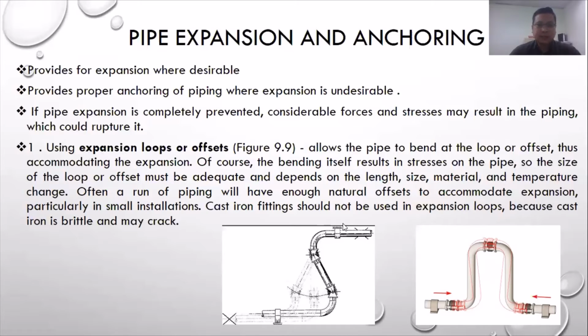Okay, the first figure uses the offset, and then we see the loops method. Using an expansion loop or offset allows the pipe to bend at the loop or offset, which accommodates the expansion. The bending itself results in stresses on the pipe, so the size of the loop or offset must be adequate and depends on the length, material, and temperature change. Okay.